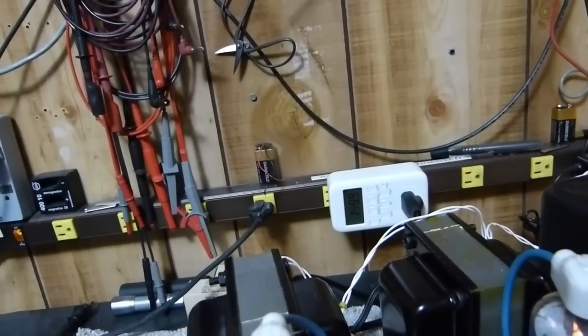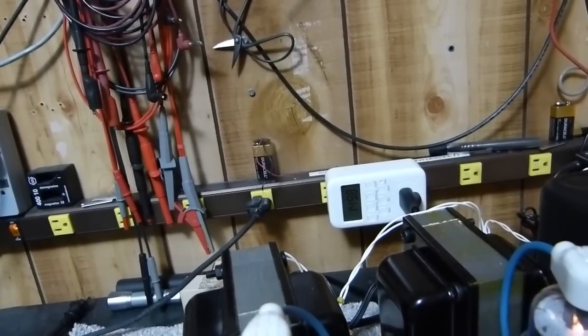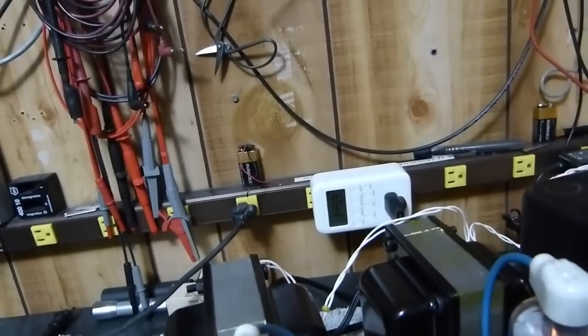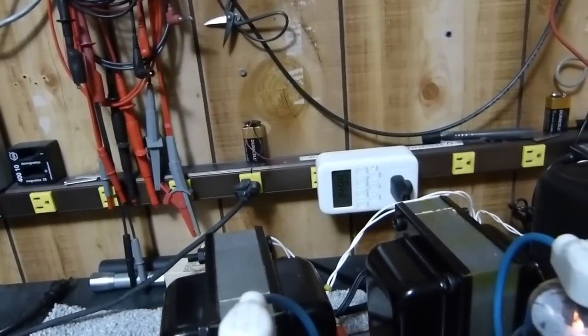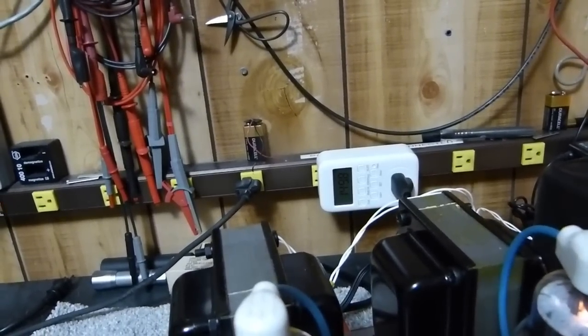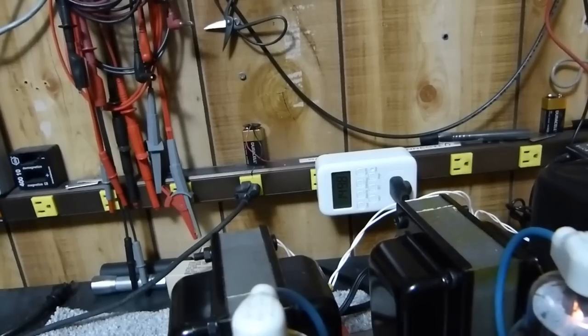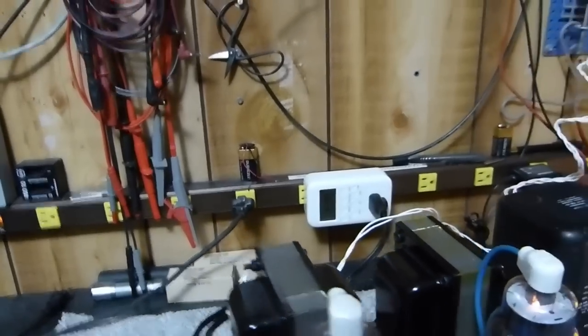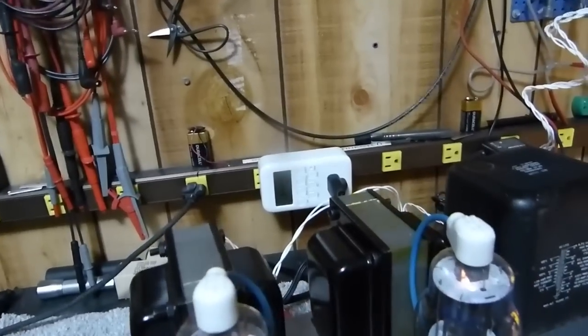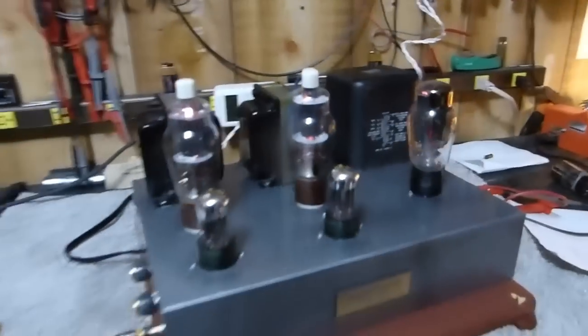1 amp times 120 volts would be 120 volt amps, so it's a little bit more than 1 amp. I've always been taught to double that for a fuse, so put in a 2 amp, probably a 3 amp, or a 2 amp slow blow, maybe a 3 amp slow blow. Don't put in a 10 amp.